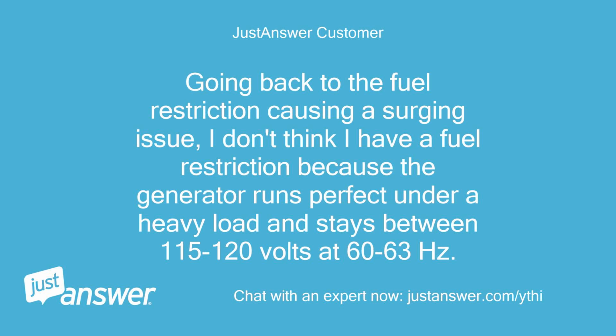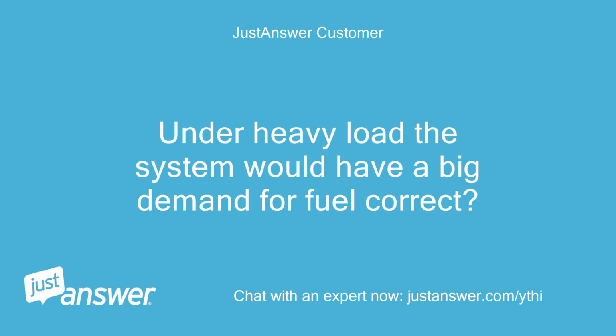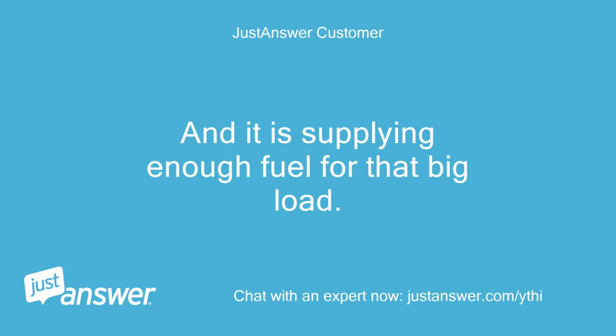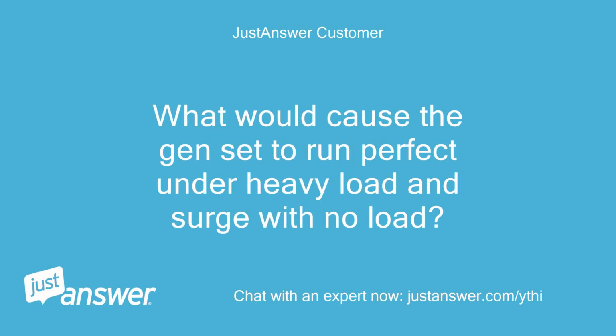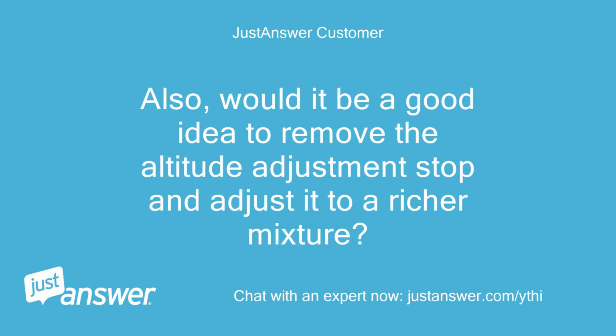Going back to the fuel restriction causing a surging issue, I don't think I have a fuel restriction because the generator runs perfect under a heavy load and stays between 115 to 120 volts at 60 to 63 Hz. Under heavy load the system would have a big demand for fuel, correct? And it is supplying enough fuel for that big load. What would cause the genset to run perfect under heavy load and surge with no load? Also, would it be a good idea to remove the altitude adjustment stop and adjust it to a richer mixture?